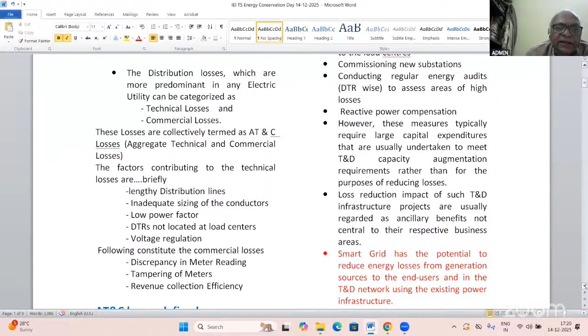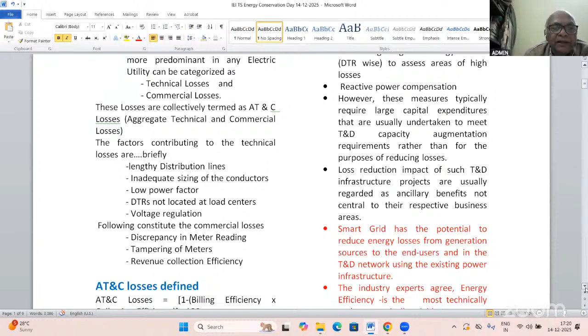The factors contributing to technical losses are briefly: lengthy distribution lines, inadequate sizing of conductors, low power factor, DTRs not located at the load centers, and voltage regulation not properly controlled.